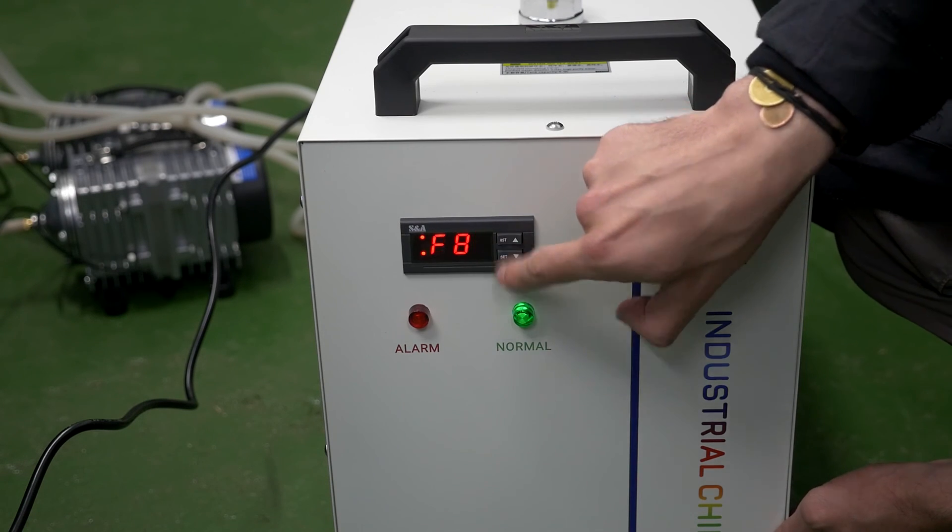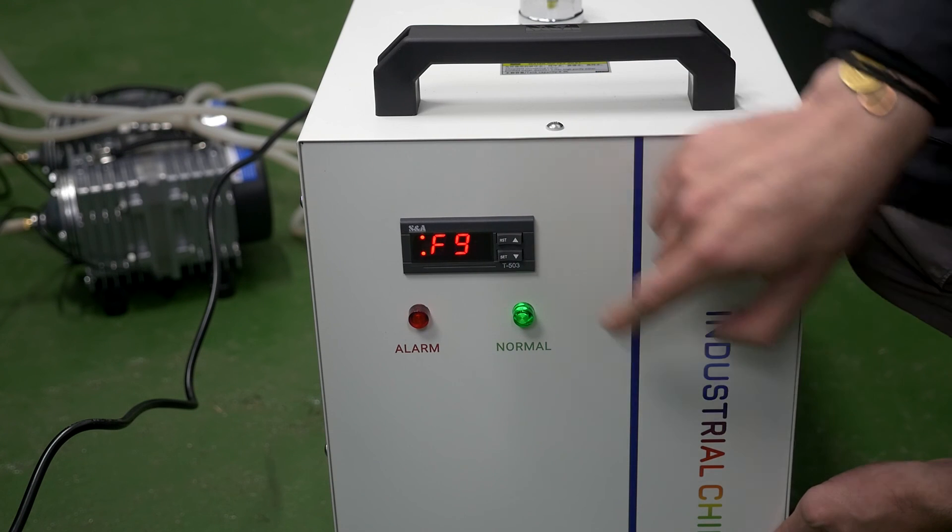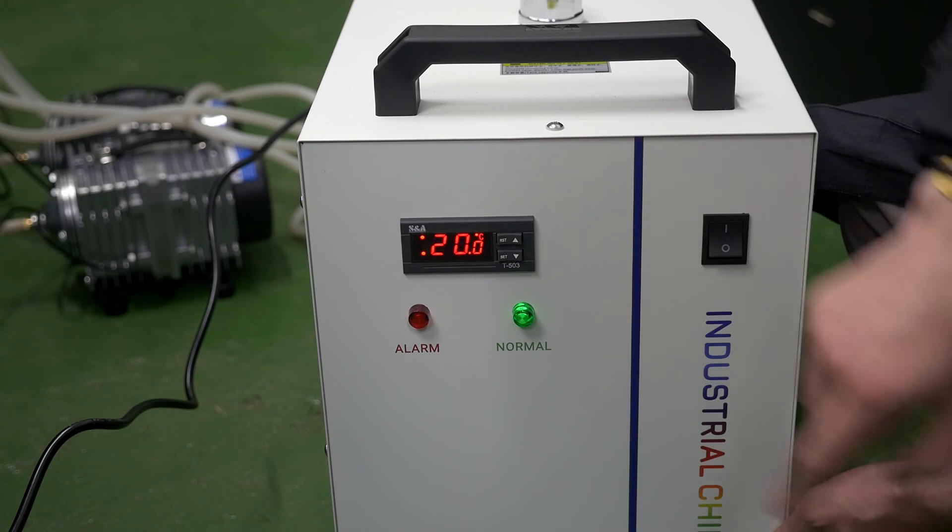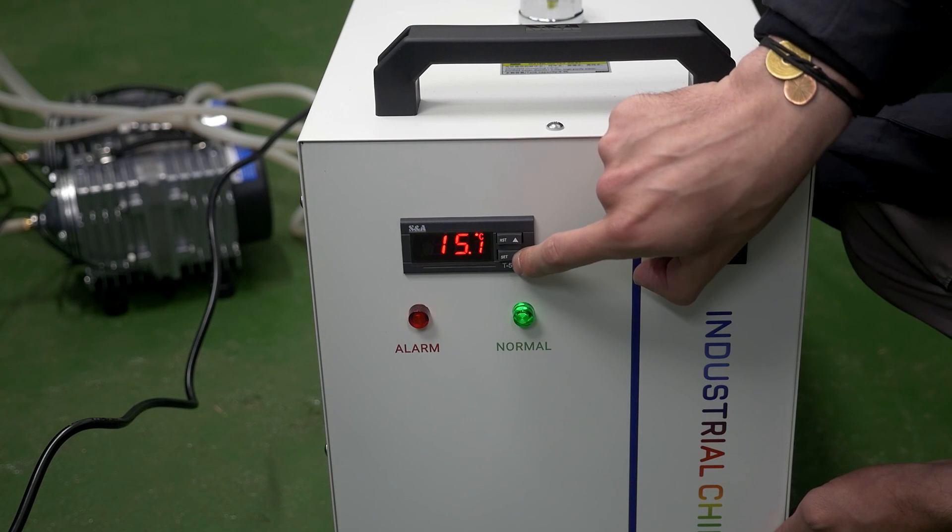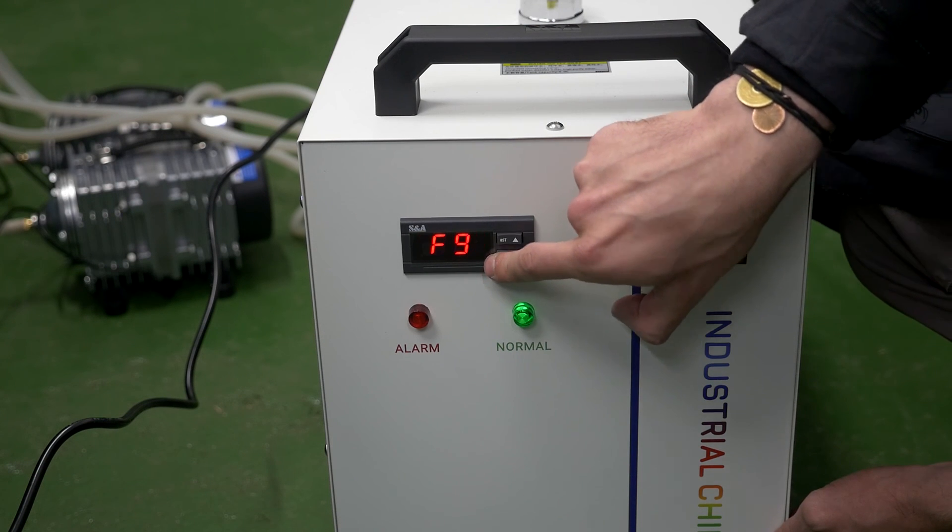Select F9 and press set. Set the value in the range 12 to 18 but not below the dew point of your room and press set. This parameter sets the lower limit of the chiller water temperature.